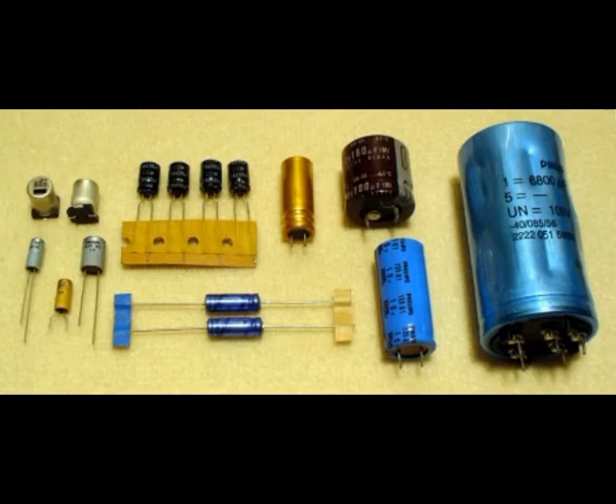If the ripple current exceeds the rated value, the corresponding heat generation exceeds the capacitor's temperature limit and may destroy the internal structure, voltage proof, and boiling point of the capacitors. Then the components tend to short-circuiting, vent opening or explosion. Ripple currents higher than rated values are possible only with forced cooling.